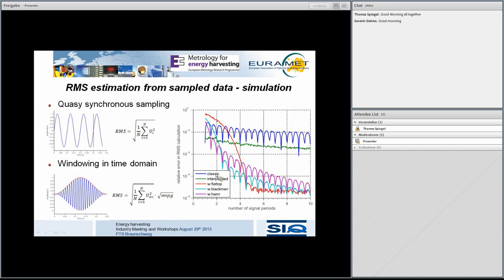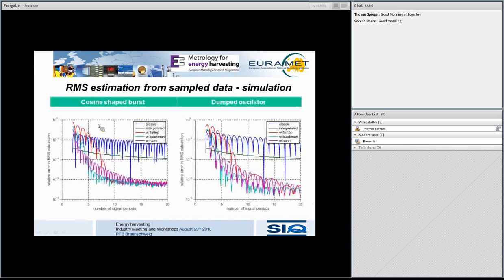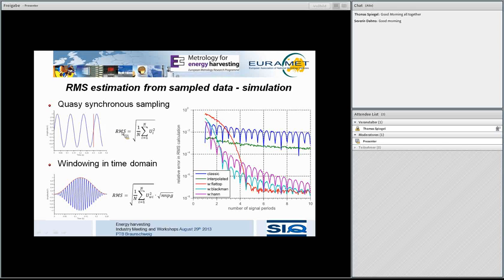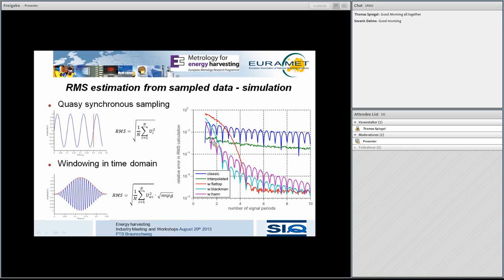If we look at what happens with each approach, for a sine wave with a little harmonic content added, a simple classic use of the formula without any synchronism gives quite high errors — though these errors go down when we're near an integer number of signal periods. Using quasi-synchronous sampling with interpolation, so we really find the integer number of cycles, reduces these errors by a factor of 10 to 100, but that's still not enough if we only use a few signal periods.